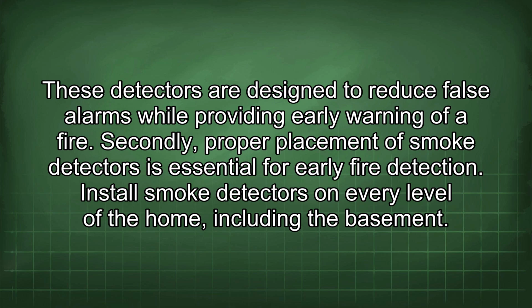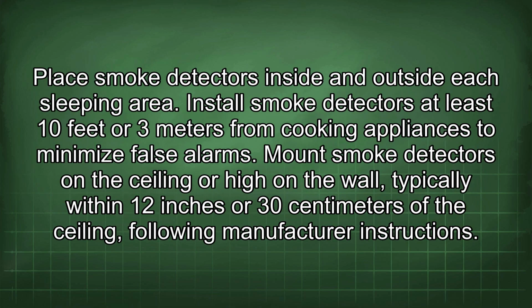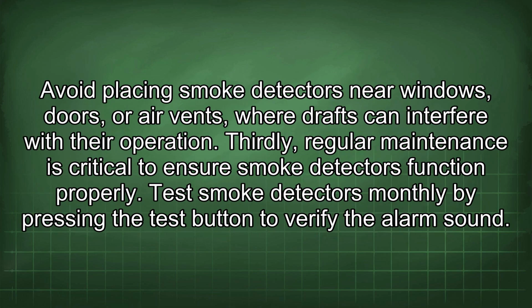Secondly, proper placement of smoke detectors is essential for early fire detection. Install smoke detectors on every level of the home, including the basement. Place smoke detectors inside and outside each sleeping area. Install smoke detectors at least 10 feet or 3 meters from cooking appliances to minimize false alarms. Mount smoke detectors on the ceiling or high on the wall, typically within 12 inches or 30 centimeters of the ceiling, following manufacturer instructions. Avoid placing smoke detectors near windows, doors, or air vents, where drafts can interfere with their operation.